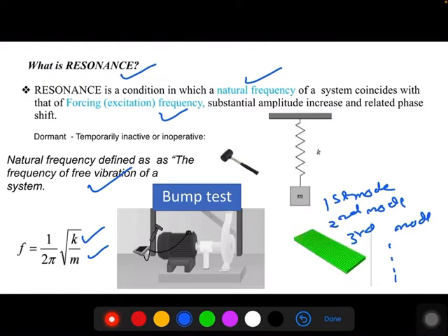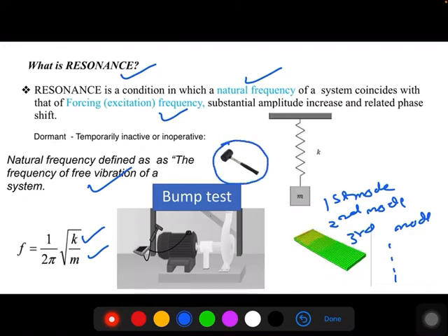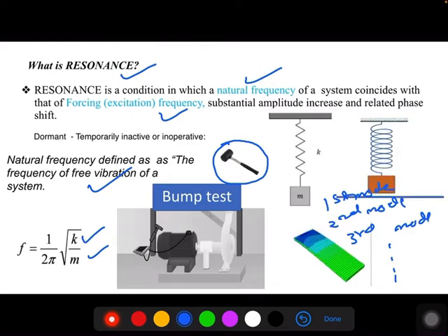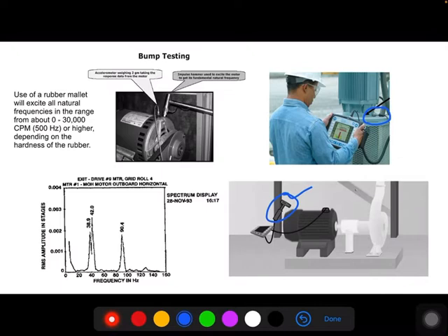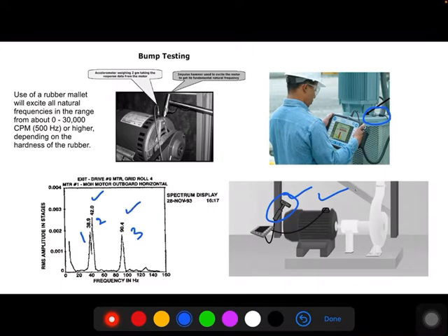Now, how do you determine the natural frequency of any component? In a bump test, you hit the component using a mallet or a hammer and connect a vibration analyzer with an accelerometer near that hitting point. You will then get a spectrum in the vibration analyzer. For example, a component might have three natural frequencies: the first natural frequency around 38.9 Hz, the second at 42 Hz, and the third at 90.4 Hz. Using a bump test, you can determine the multiple natural frequencies of a component.